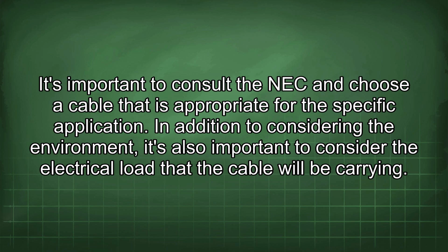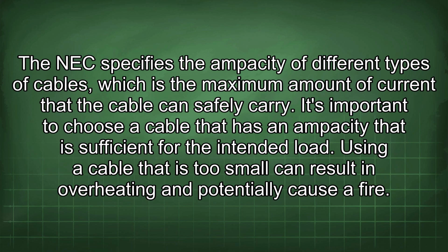environment, it's also important to consider the electrical load that the cable will be carrying. The NEC specifies the ampacity of different types of cables, which is the maximum amount of current that the cable can safely carry. It's important to choose a cable that has an ampacity that is sufficient for the intended load. Using a cable that is too small can result in overheating and potentially cause a fire.